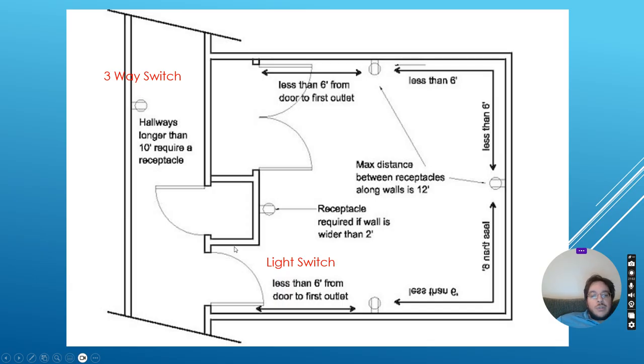Now, in Canada, the rule is a bit different. In a hallway, I need to be able to reach a receptacle within 4.5 meters. So if my vacuum cleaner is here, for example, I need to be able to get to a receptacle. So any point in the hallway should be no more than 4.5 meters from a receptacle, and I should not have to go through a door. In case I'm vacuuming and somebody's sleeping, I shouldn't have to go into the bedroom to plug in the vacuum cleaner to vacuum the hallway.